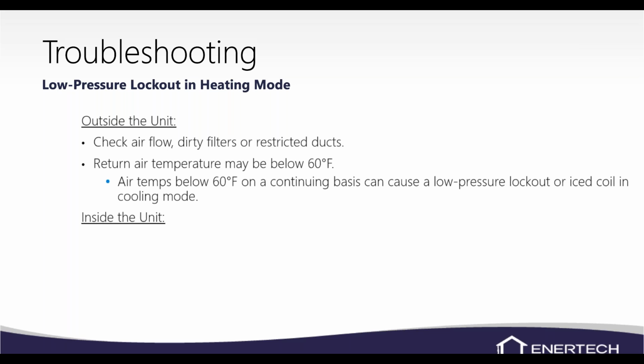If you're below 60 degrees in cooling, the coil could start to ice up. Normally, if you ever go out to a unit and it's a big ball of ice on the air coil, that's normally an airflow problem. If you have low refrigerant, the air coil might frost up, but it won't normally be a big ball of ice. That's usually caused by airflow, not enough airflow.